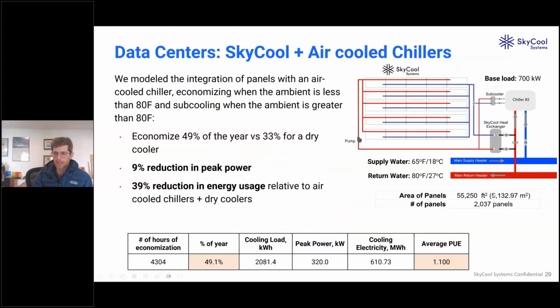So this is a case study that we've developed with data centers, for data centers. In this particular system, we're using the panels. The baseline system is a chilled water system with air-cooled condensers on the chillers, and there are dry coolers, which are providing some economization in the winter cooler seasons.